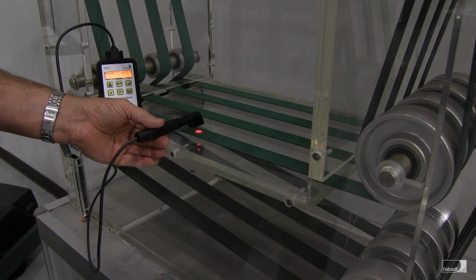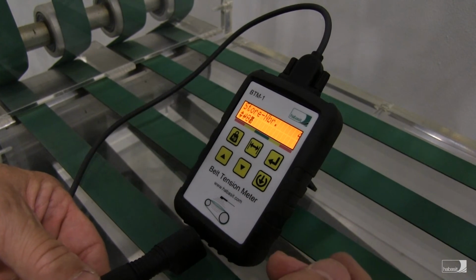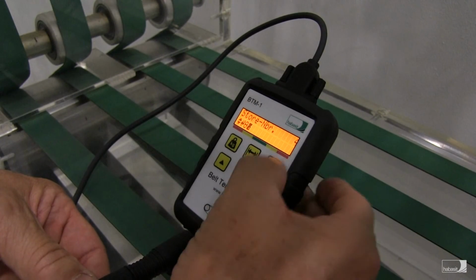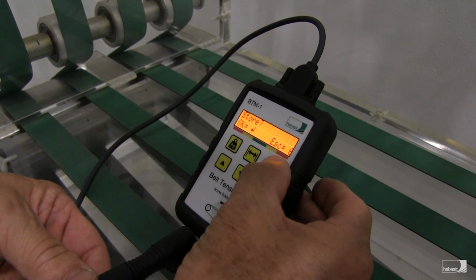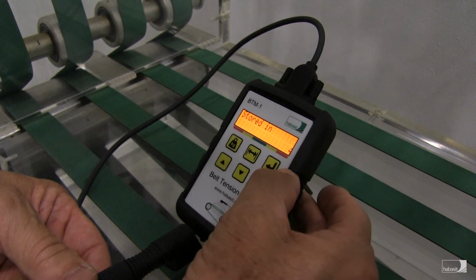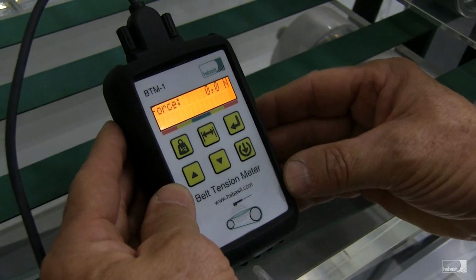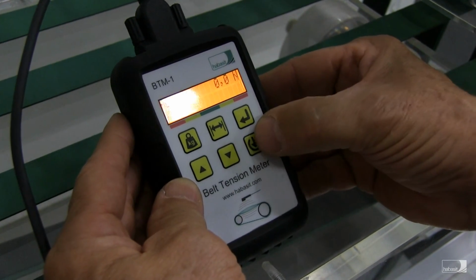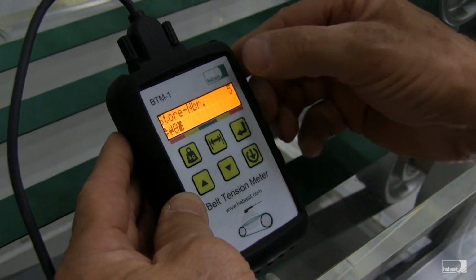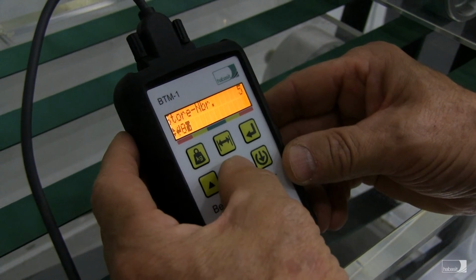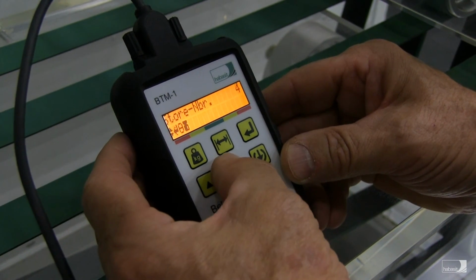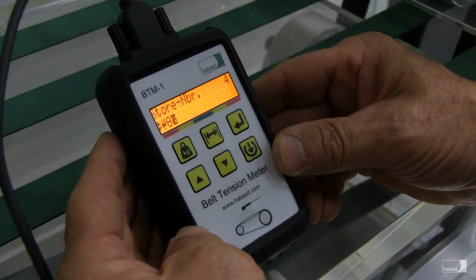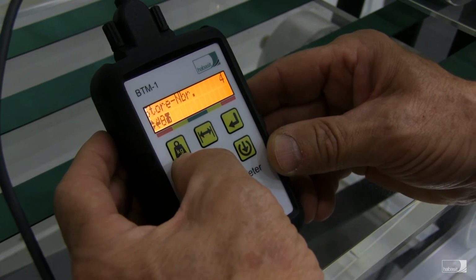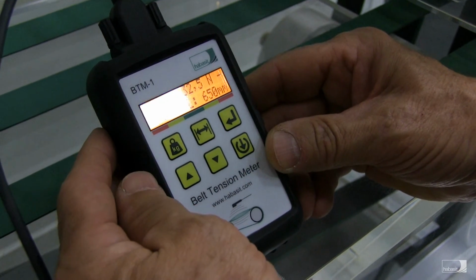There's an audible tone when the force measurement is completed. Press the down arrow key and it gives you the option to store the measurement. Press the enter key, store OK, press enter again, stored in location number 4. To recall a stored value for a measurement that you've stored, press the down arrow key. It shows the store number. Use the arrow keys to go up or down to select the location where you stored your measurement, and then press the kilogram key and it will recall the measurement for you.